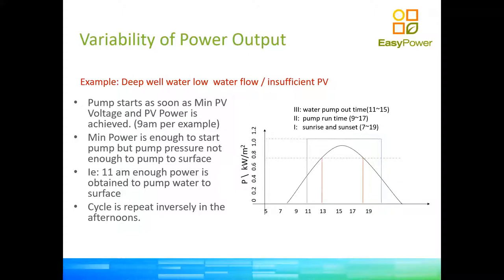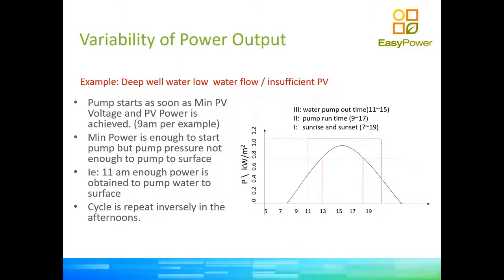In this example, a pump only starts producing water at the surface at a certain time of day, even though the pump actually started probably two hours earlier. In some applications you have to build up pressure before you start to produce — especially on borehole applications, where you need to oversize your PV array quite a bit to ensure early production. This is not necessarily the case when the pump discharges to atmosphere, such as filling a pressure tank on the surface.